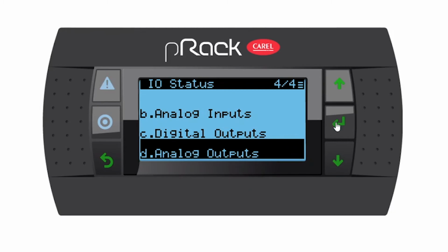analog outputs and enter. But as you can see, I'm not able to enter the analog outputs menu. And the reason for this is we haven't assigned an analog output. In the wizard, we said it's normal on-off fans and CR2 compressor and on-off compressors. So there's no 0 to 10 volt assigned on this pRack controller, and that's why you are not able to enter the analog outputs menu. So that's me and how I assign the digital inputs and outputs for a Bitzer CR2 compressor and also just for a normal rack. So thank you guys for watching, and I'll see you in the next one.